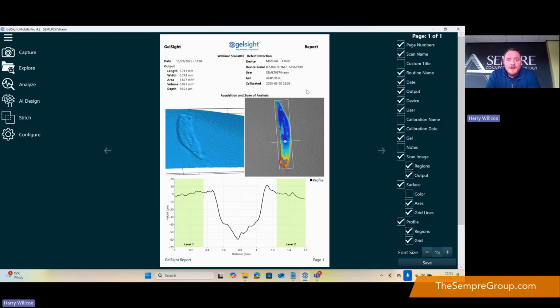Every time we take a scan, we're capturing the device that's used. So I've got the L1600 lens, the device serial numbers, user, gel, and the last time it was calibrated for that sort of traceable report that you would need. Okay, and from here I'd be able to either print that off or save that onto the laptop, send that to a customer or to one of the MRO teams within the business to make a decision as to whether that defect is acceptable or not.